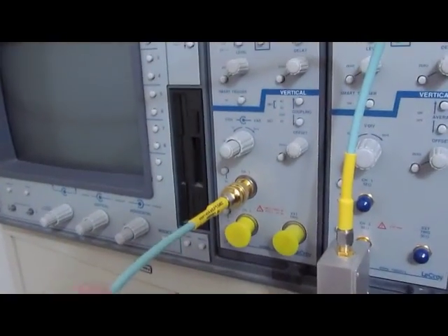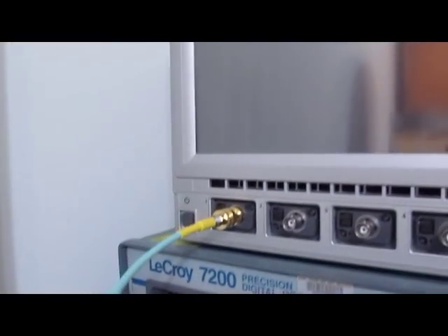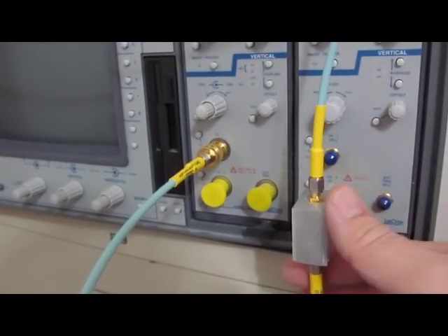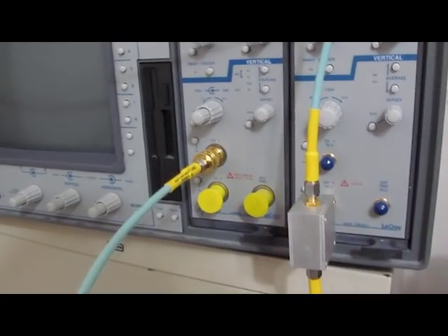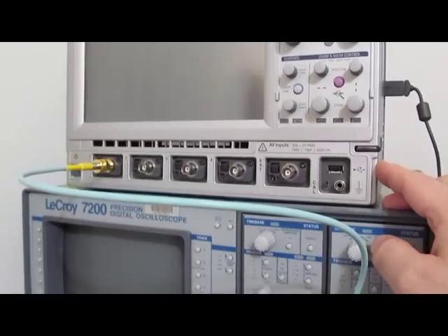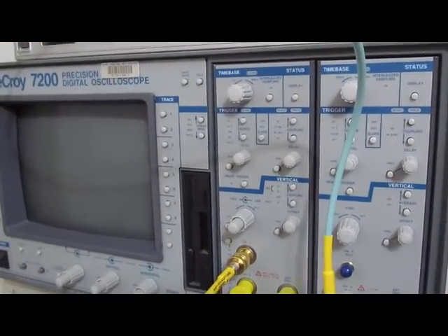One-legged coax going up to the 7242, the other running up to our WaveRunner. I'll just enable this feature and we'll measure the fall times on both of them. The WaveRunner should show a significantly quicker fall time, but I guess we'll go ahead and measure it and just see where it's at.